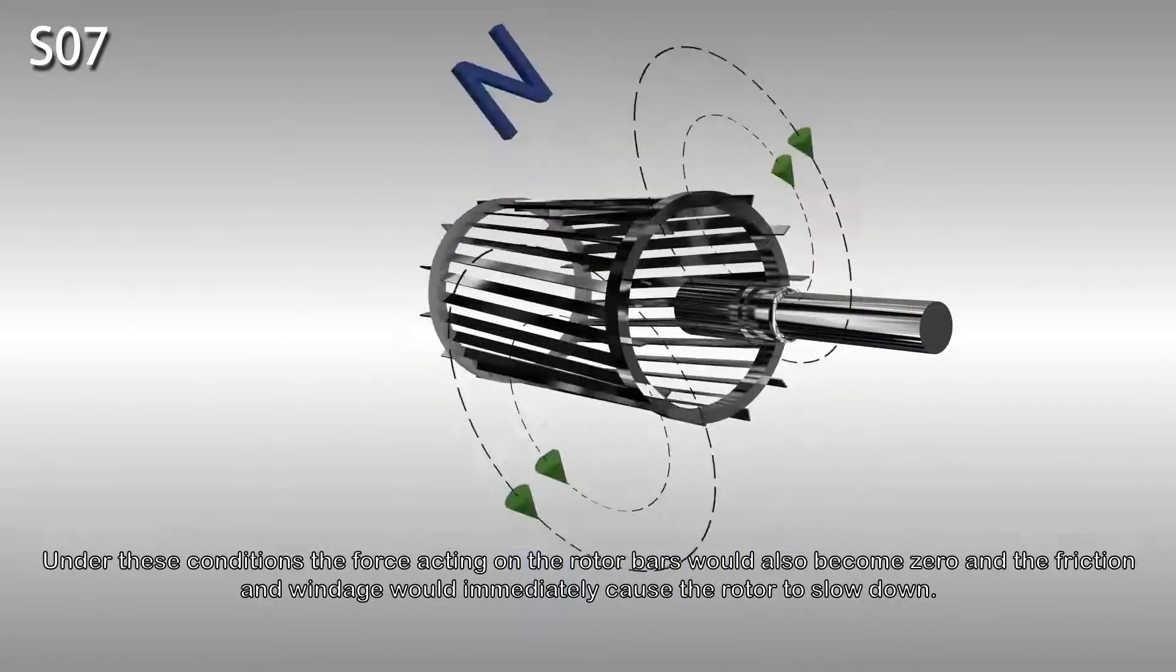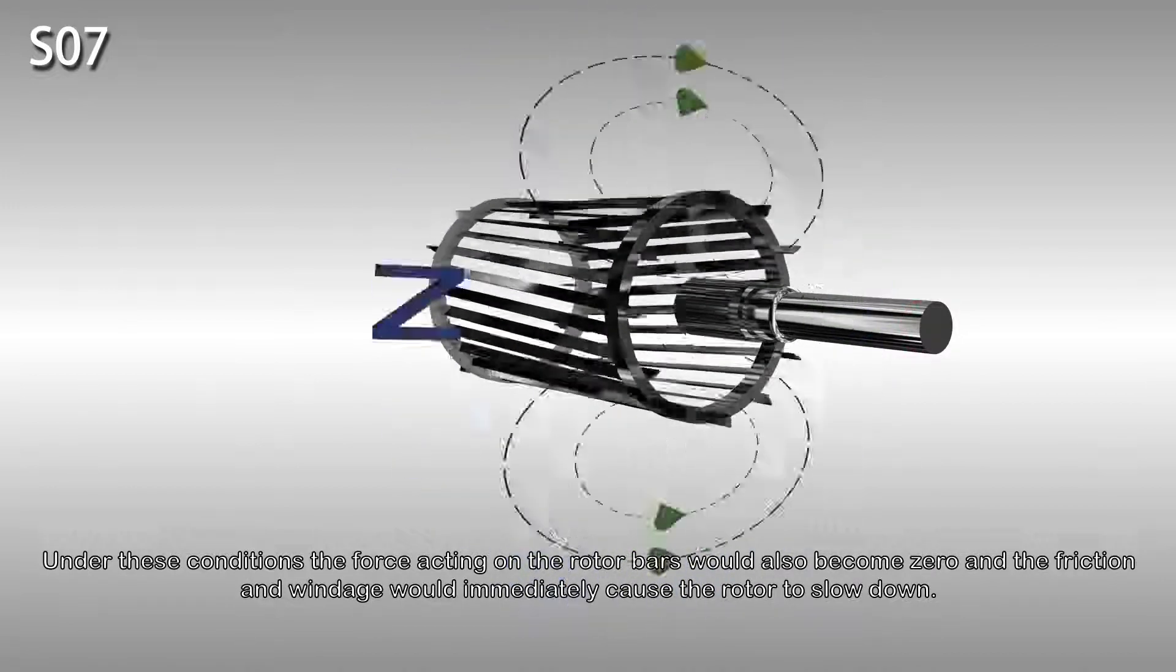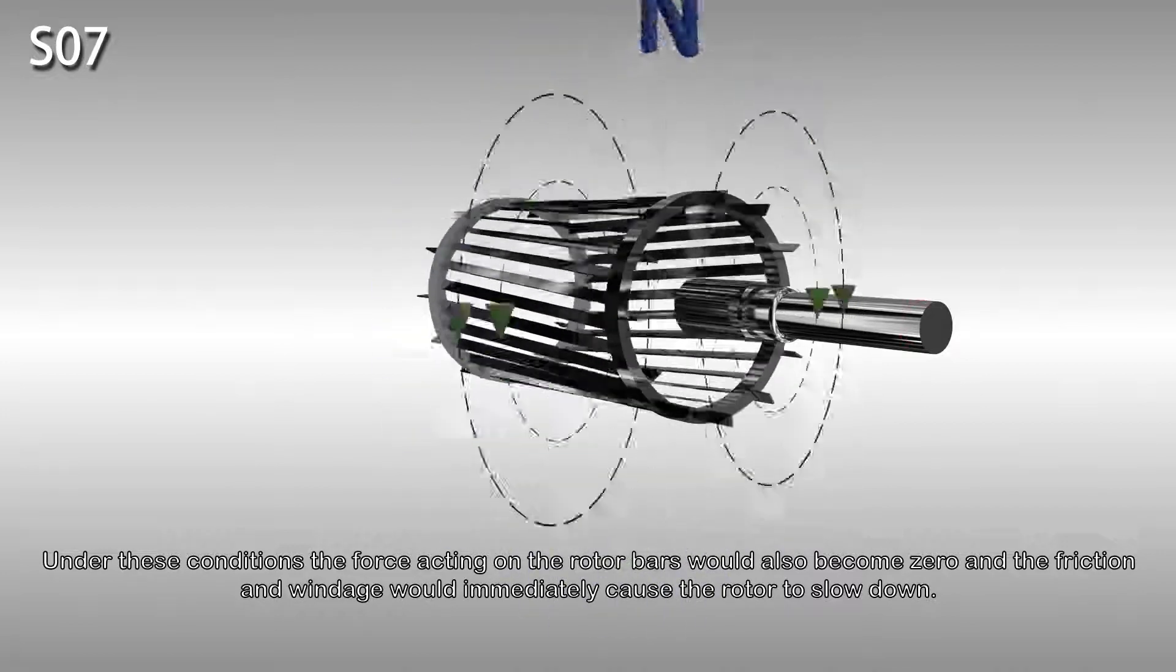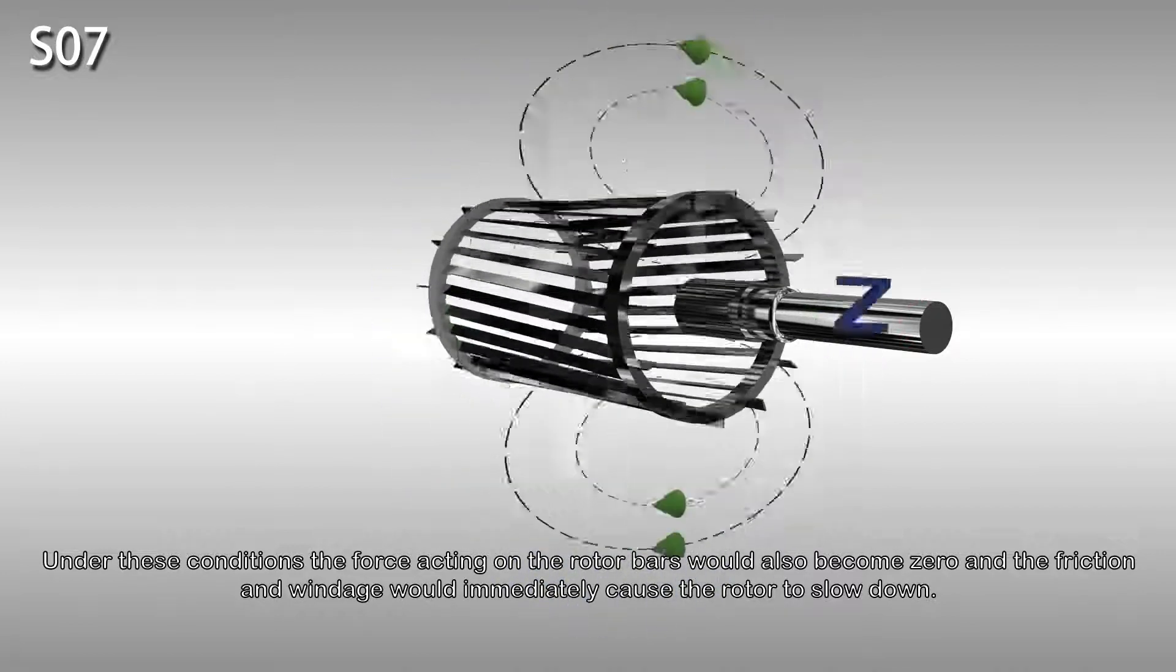Under these conditions, the force acting on the rotor bars would also become zero and friction and windage would immediately cause the rotor to slow down. The rotor speed is always slightly less than the synchronous speed in order to produce a current in the rotor bars sufficiently large enough to overcome the braking torque.